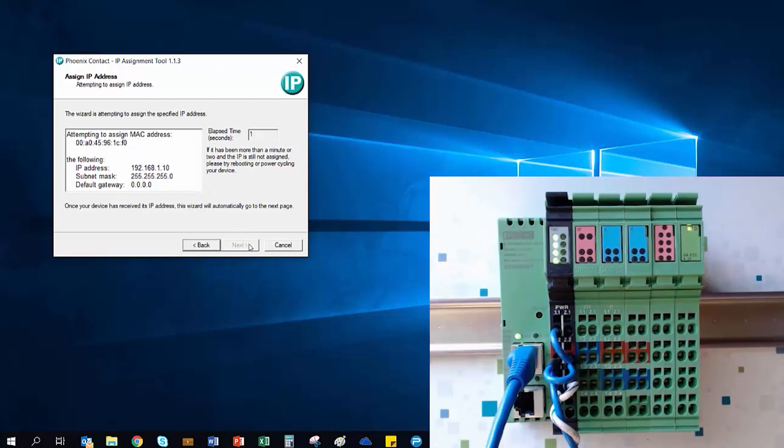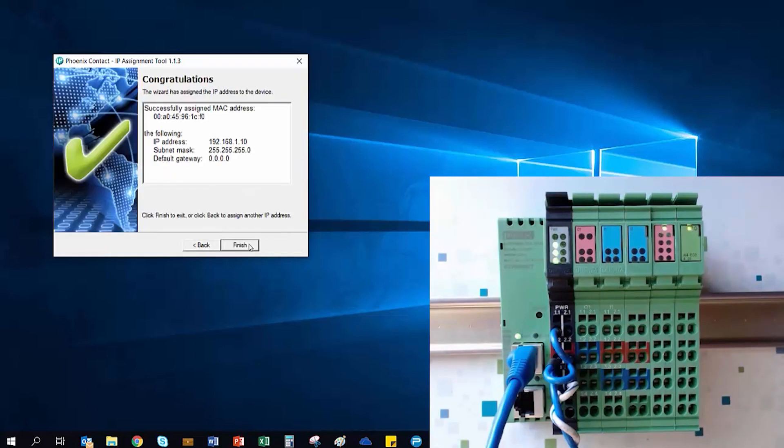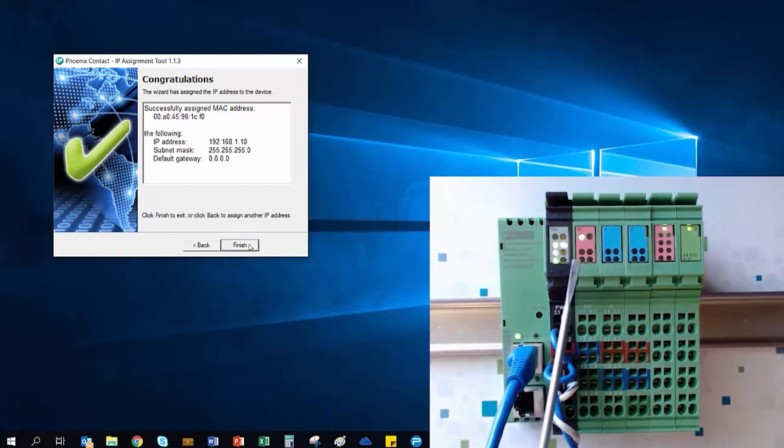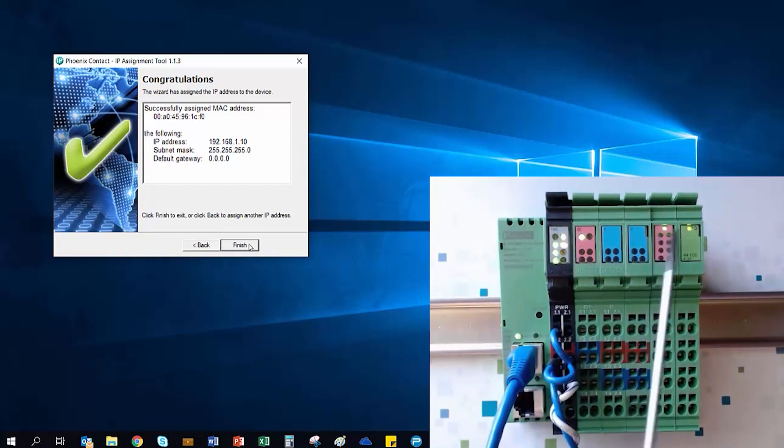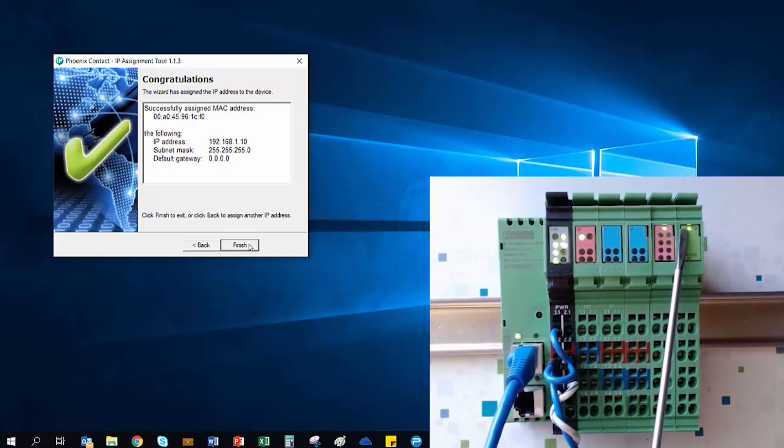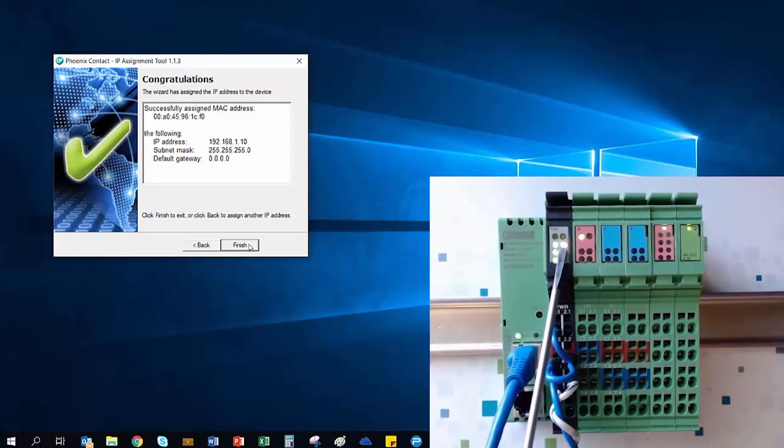Now we wait for this request to be acknowledged by the bus coupler and for the bus coupler to accept the changes. You'll notice the LEDs on the local I.O. modules have gone on solid green, and there is a new amber light on the BK, which indicates that we are in a mode called Plug and Play.